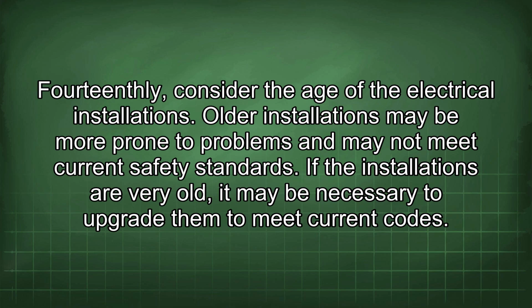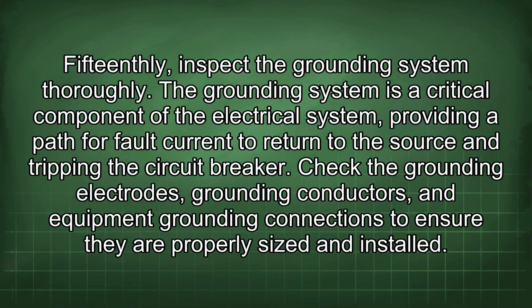Older installations may be more prone to problems and may not meet current safety standards. If the installations are very old, it may be necessary to upgrade them to meet current codes. 15thly, inspect the grounding system thoroughly. The grounding system is a critical component of the electrical system, providing a path for fault current to return to the source and tripping the circuit breaker. Check the grounding electrodes, grounding conductors, and equipment grounding connections to ensure they are properly sized and installed.